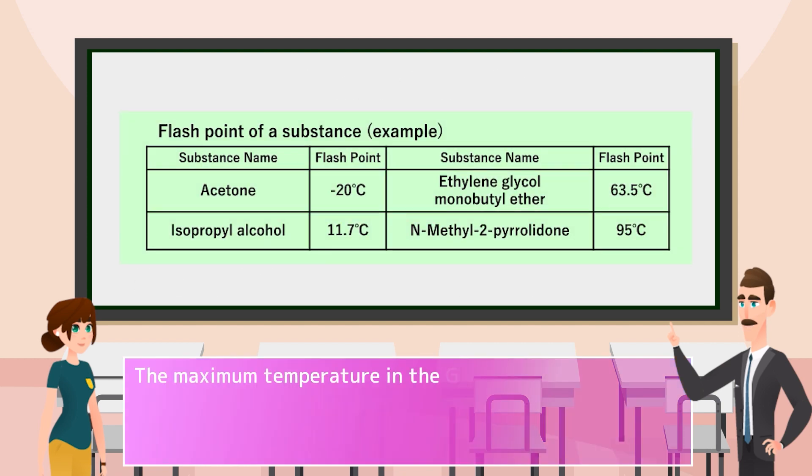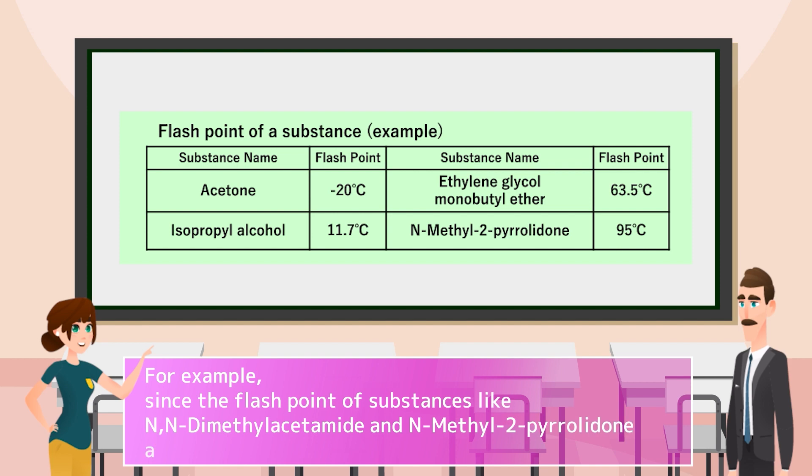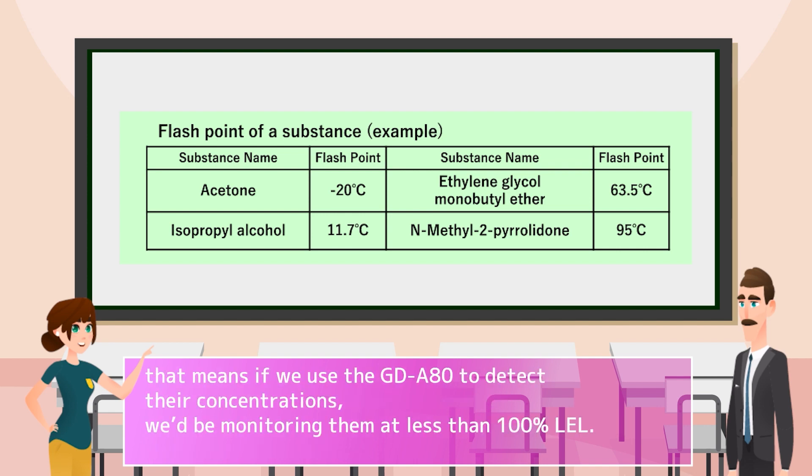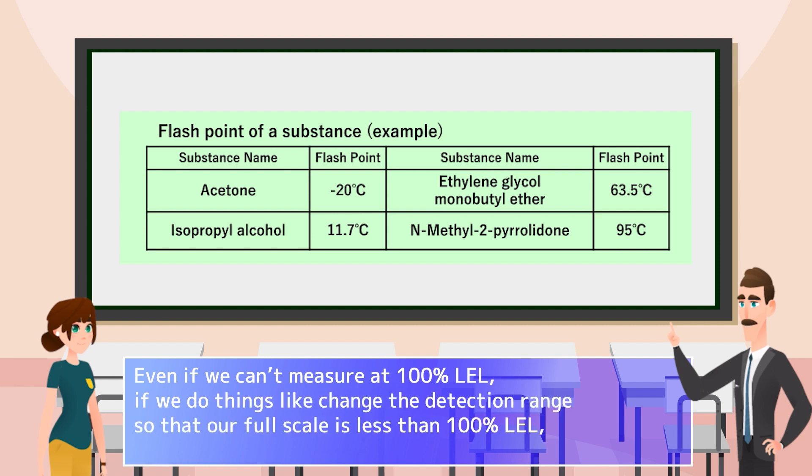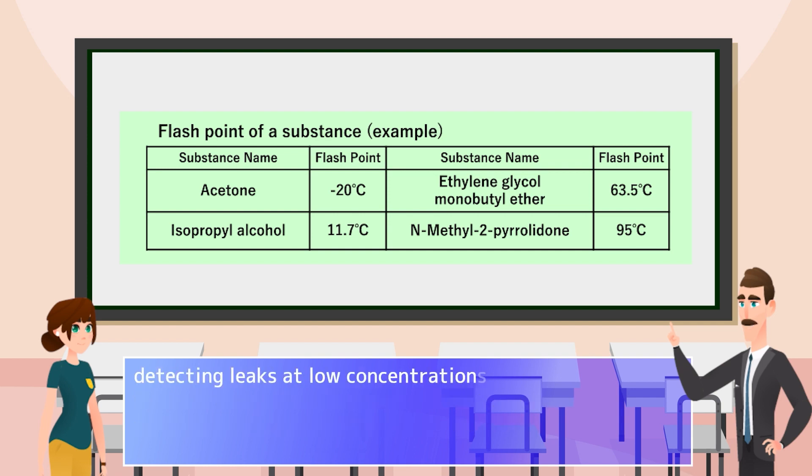The maximum temperature in the GDA80's operating temperature range is 53 degrees Celsius, right? For example, since the flash point of substances like N,N-dimethylacetamide and N-methyl-2-pyrrolidone are higher than 53 degrees Celsius, that means if we use the GDA80 to detect their concentrations, we'd be monitoring them at less than 100% LEL. Even if we can't measure at 100% LEL, if we do things like change the detection range so that our full scale is less than 100% LEL, detecting leaks at low concentrations would still be a way to prevent explosions.